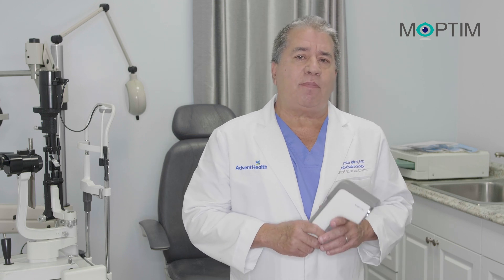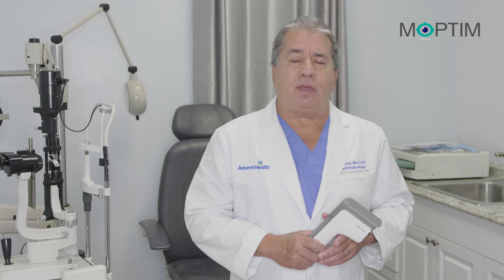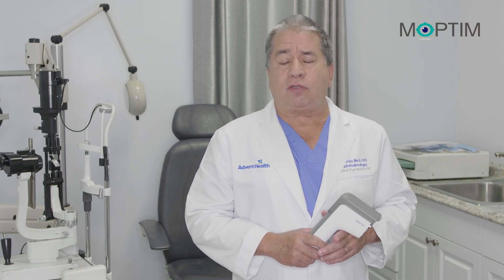And today I'm here to talk to you about the EZ-Ref by MOPTIM. The EZ-Ref is an autorefractor based on Hartmann-Shack technology, which gives it more accuracy.